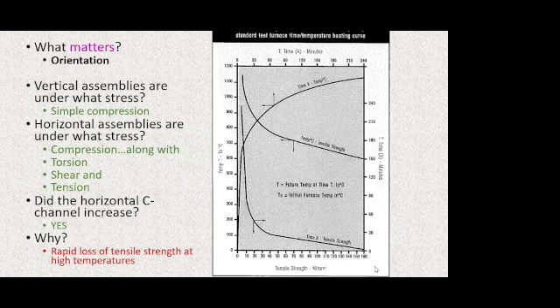That clevis clamp, that all thread rod, that cracked concrete anchor, all of those things are designed down to their residual strength at 2000 degrees. And so it goes with fire rated duct. All of these duct systems have a steel backbone and an exposed steel hanging system. And this is why I say there's no such thing as minimum SMACNA in fire duct land, because minimum SMACNA is designed to hold duct up at 70 degrees ambient, plus or minus creature comfort temperatures. Fire rated duct systems need to stay up there at 2000 degrees for hours at a time.